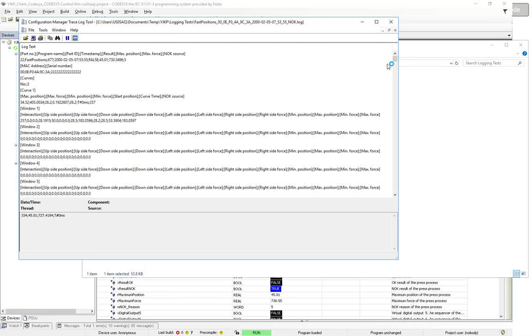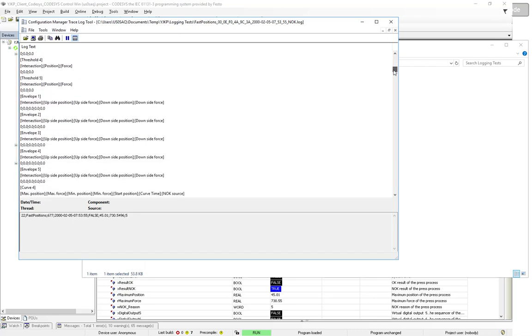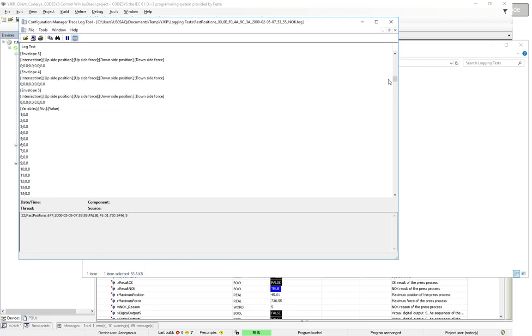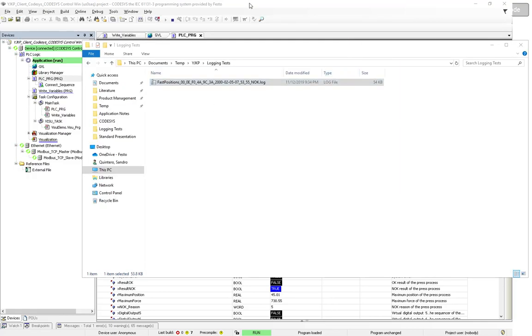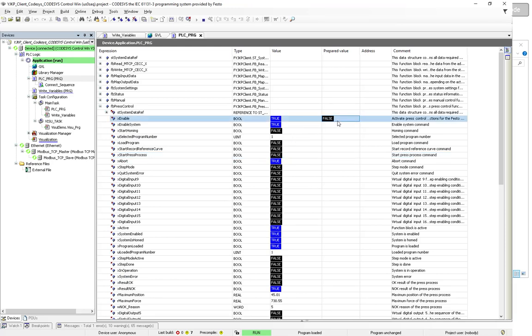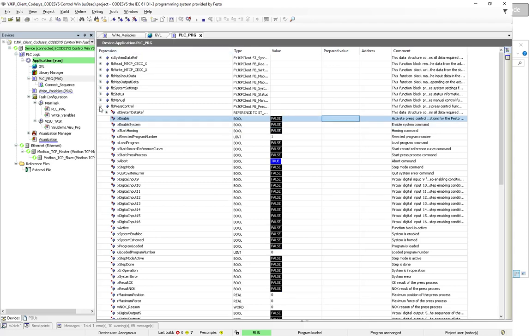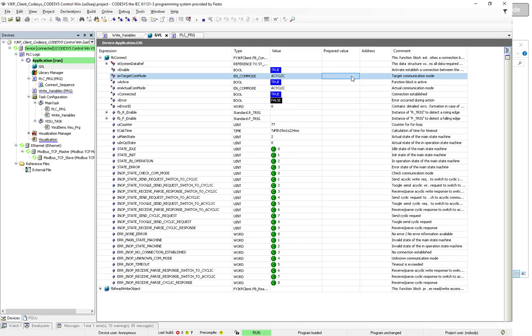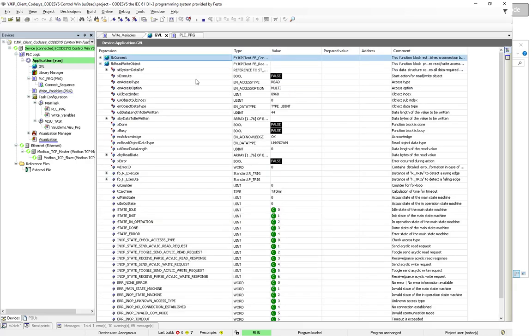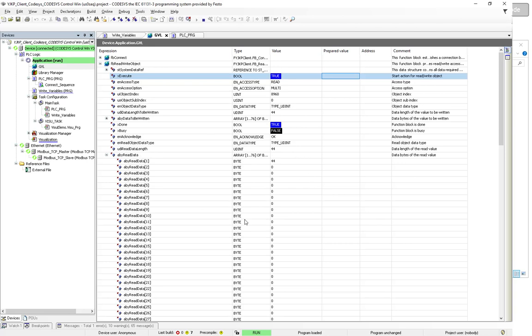The log file includes a lot of different information from the press process — whether it was OK, which program was running, and so on. Right now, we're focused on the variables section. Looking at variables, it says zero and zero — everything is set to zero. Let's see what happened. I'll disable this for now, go back to FB Connect, switch to acyclic, and read to see what's there. It says everything is empty.